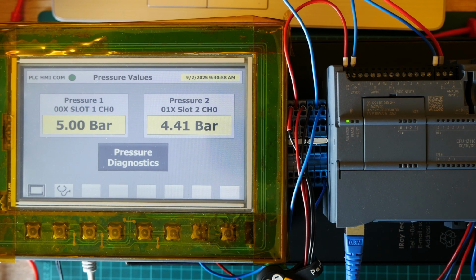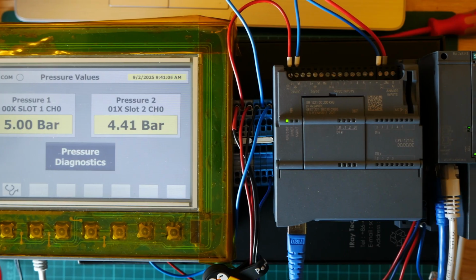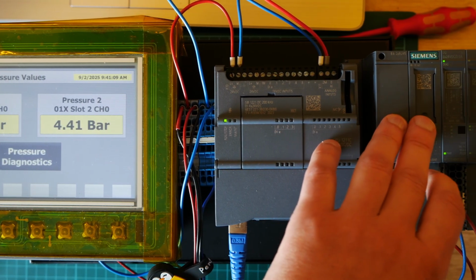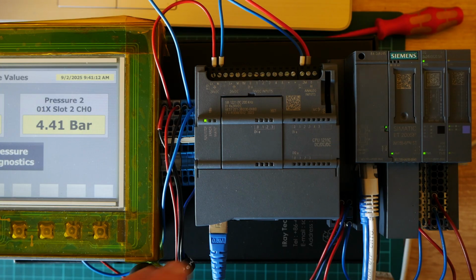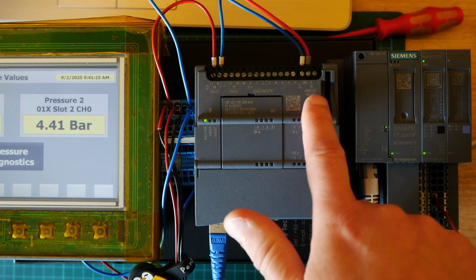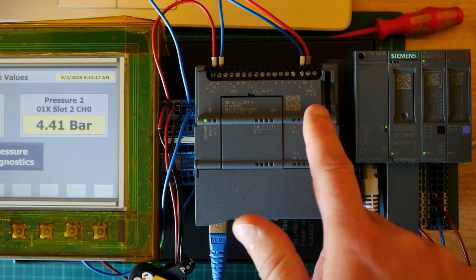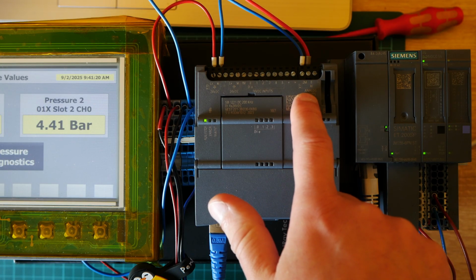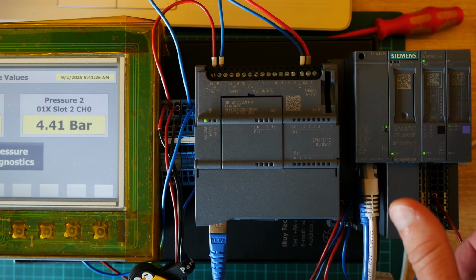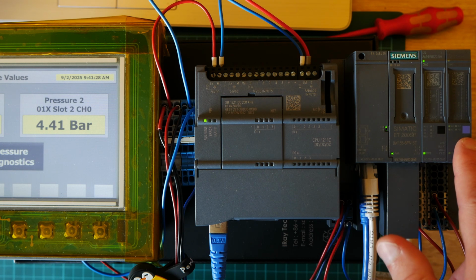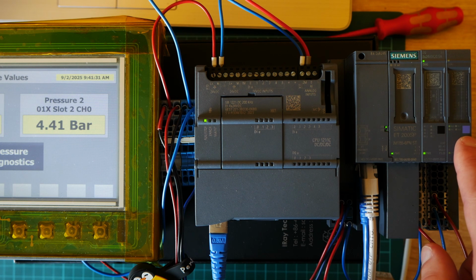So today I'm gonna talk about the Siemens S7-1200 family PLC ET200 SP modules, and I will talk about the analog input signal. So here is a wired analog input signal from 0 to 10 volts, and on this card it's wired 4 to 20 milliamperes to wire a transducer sensor.